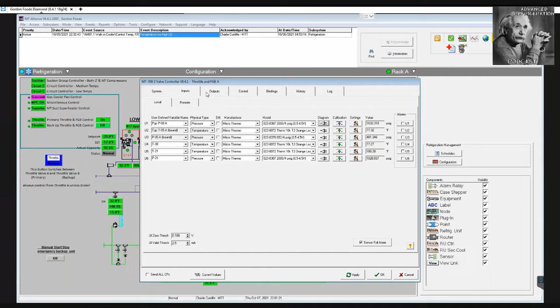Okay, so it's a Sporlan. Now there are other valves we look at. We're agnostic, we can use an Alco, a Danfoss, or a Sporlan. So this store has a GC30. It's programmed radius, what does that mean? The inlet is coming on the radius of the port. And they used an SDR4 here for valve 2. Again, Sporlan or the other manufacturers I told you about, this happens to be an SDR4, and here's the current percent open.